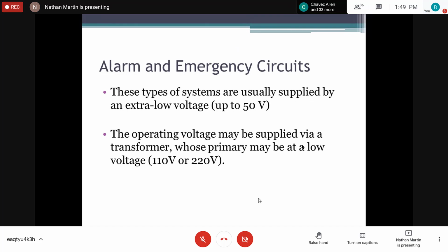All right, alarm circuits. These types of system are usually supplied at extra low voltage, right? Rather than 110 or 220 volts, we're talking about 50 volts, so we're talking about the use of a transformer, right? Hence, these cannot be in the same conduit as the low voltage devices. So if we're using trunking, we have to use segregated trunking with different compartments. If we're using conduits, the conductors for these, the cables, must be drawn in separate trunking or conduits, right?